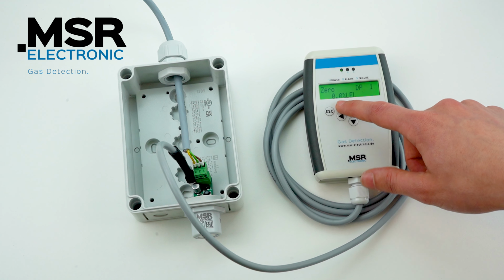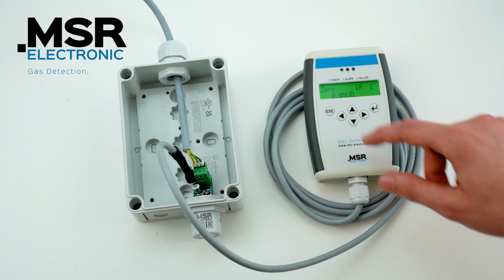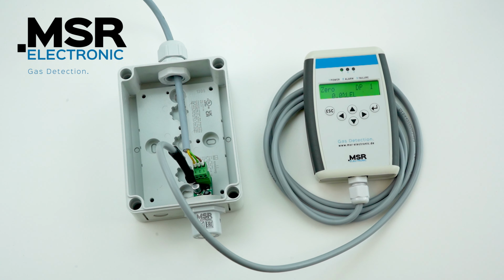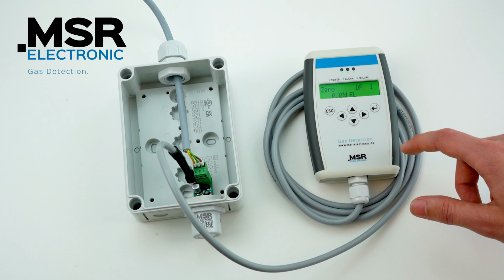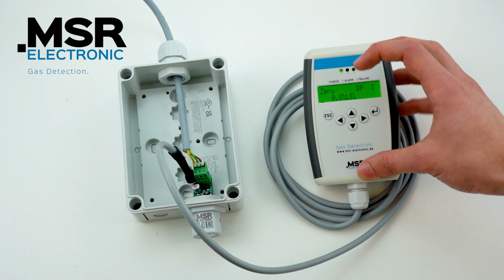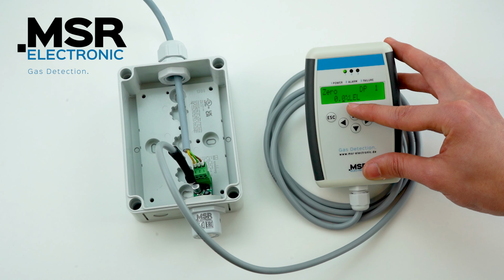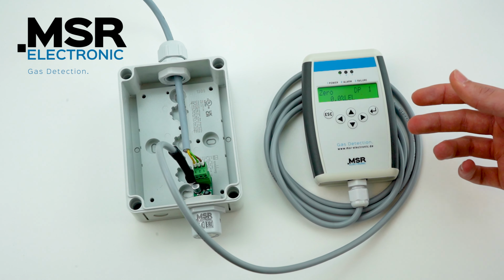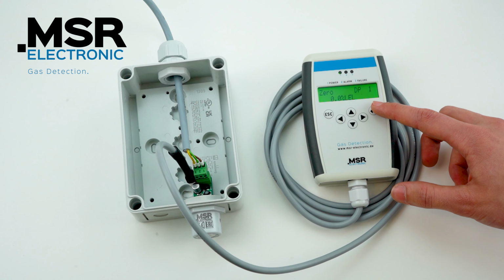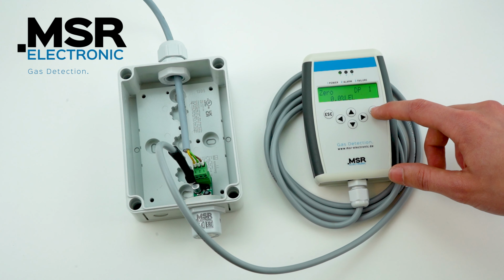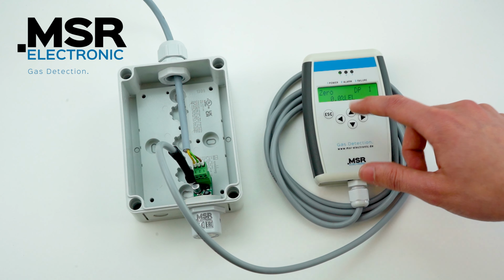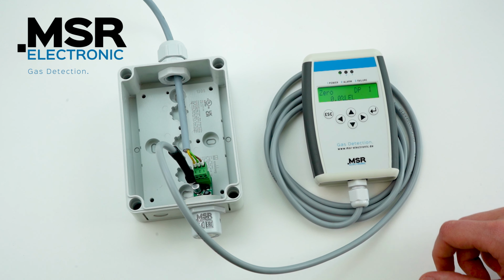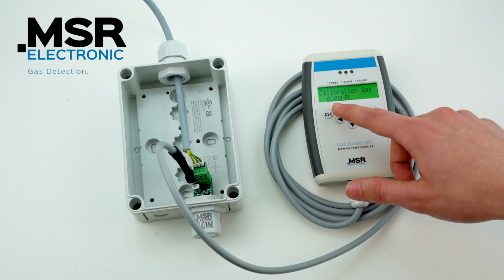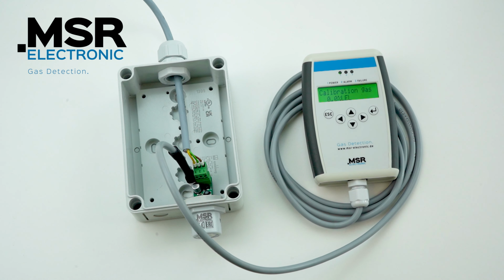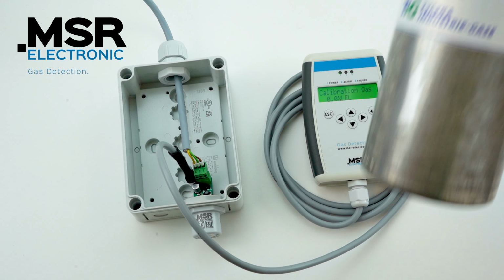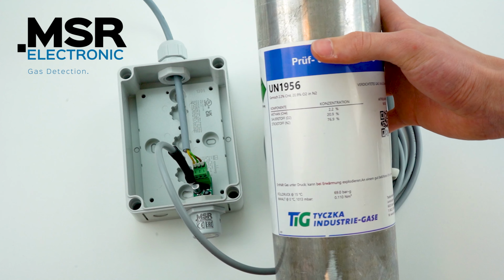To start the 0-point calibration, we press the enter button once. The current measured value of the sensor is then displayed. Pressing the enter button again starts the calculation of the new 0-point. During this process, we can see an underline running at the bottom of the screen, indicating the calculation mode. After about 10 seconds, the value can be saved by pressing the enter button again. If a zero gas is required for the zero calibration, the gas exposure time must be extended accordingly. For more information, please refer to the sensor user manual.